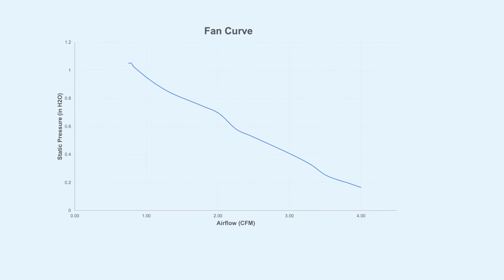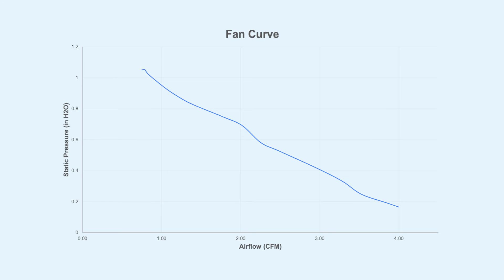Now before we look at a few examples let me give you a quick tip. Stay away from the red zone, which is the small area on the left side of the curve. This is where you're going to have issues with a lot of noise, a lot of vibration, and your fan will fail early. So stay in the green zone where your fan will blow more air and will last a lot longer.